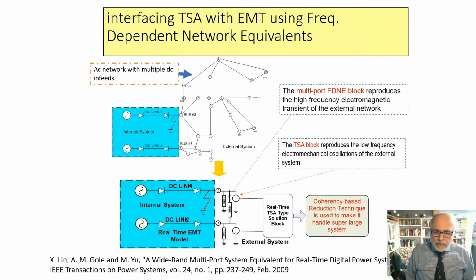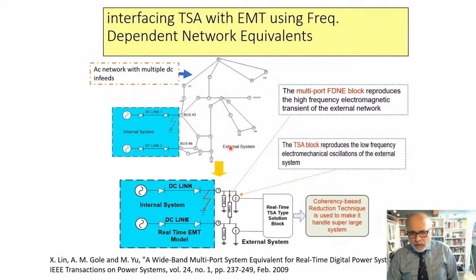Here is an example of simulating a large AC-DC combined system. You have an AC network with multiple DC infeeds on the right-hand side, and 2 HVDC links terminating in this area on buses number 3 and 8. These can be modeled on an EMT program, while the rest of the network, being mostly AC, can be modeled on a transient stability analysis program. One of the things the transient stability program does not do is represent higher frequencies.